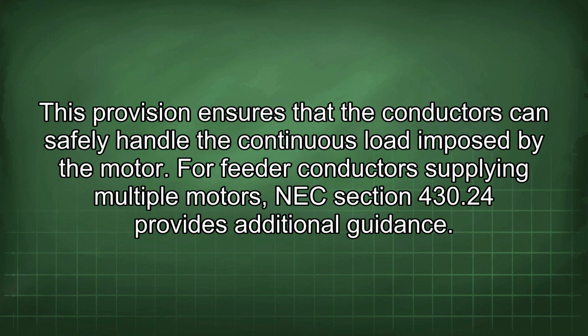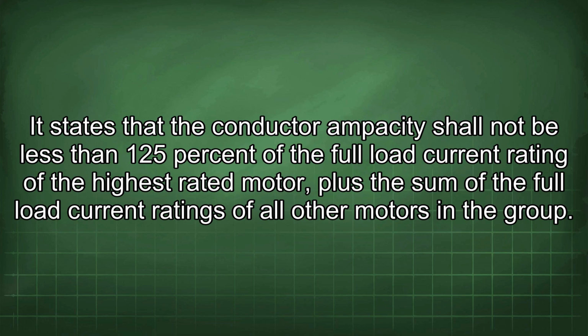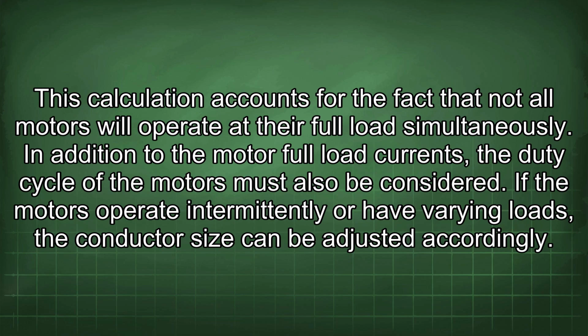For feeder conductors supplying multiple motors, NEC Section 430.24 provides additional guidance. It states that the conductor ampacity shall not be less than 125% of the full load current rating of the highest rated motor, plus the sum of the full load current ratings of all other motors in the group. This calculation accounts for the fact that not all motors will operate at their full load simultaneously. In addition to the motor full load currents, the duty cycle of the motors must also be considered. If the motors operate intermittently or have varying loads, the conductor size can be adjusted accordingly.